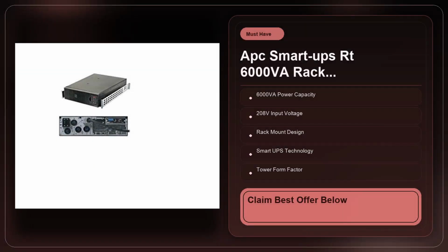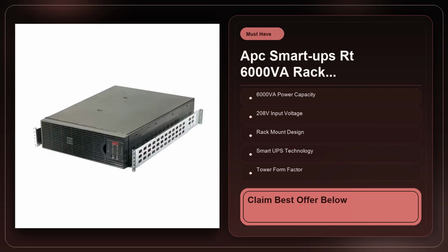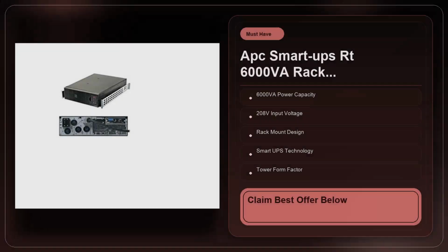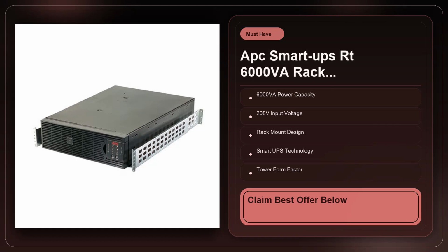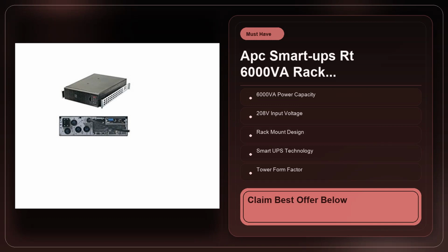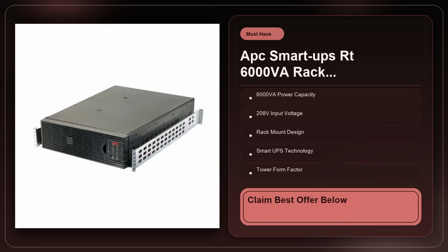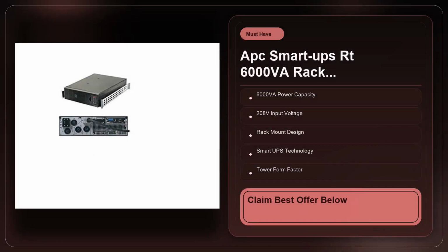On the flip side, there are a few trade-offs that matter once you have the unit installed. The Smart UPS RT is a fairly heavy piece of equipment, tipping the scales at around 350 pounds. That means you'll need a sturdy rack, proper floor reinforcement, and possibly a service lift if you're installing it on an upper floor. It's not a unit you can just bump up on a tabletop and expect it to stay put. Another practical weakness is that the UPS doesn't come with a built-in extended runtime battery pack. You have to purchase the external battery modules separately if you want runtimes beyond the 15-minute baseline. That adds cost and complexity, especially if you need multiple modules for redundancy.